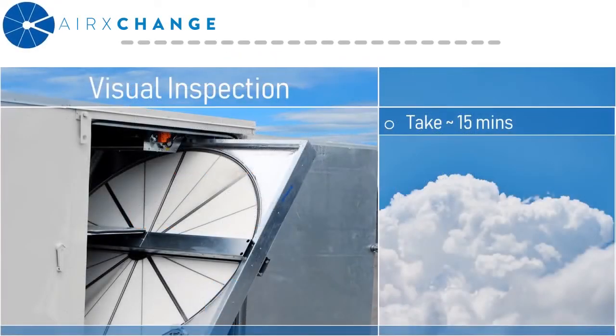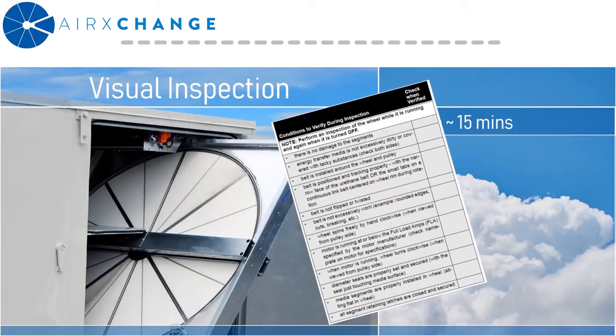So what should be included in a visual inspection? In our operation and maintenance manual, we have developed this checklist to simplify the process and suggest the items you should verify. The total inspection per wheel should take about 15 minutes. You want to make sure that there's no damage to the segments, that the energy transfer is not excessively dirty or covered with tacky substances.